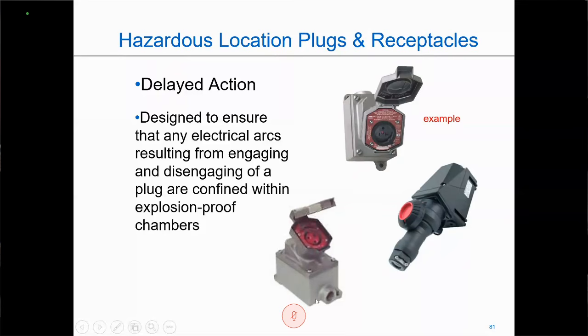This particular receptacle here is an explosion-proof Class 1 Division 1 receptacle. It is not certified for Class 1 Division 2 and would be a code violation. I'm sorry, it's not certified for Class 2. Somebody's been talking too much. It's a Class 1 Division 1 receptacle. It's not certified for Class 2 combustible dust. This particular unit here, the dust would interfere with the switching mechanism here. So that's why it's not certified. So this unit's approved for Class 1 Division 1, Class 1 Division 2, but would be a code violation to use it in a Class 2 area with combustible dust. Gets back to what we talked about a couple times earlier. Just because a piece of equipment is explosion-proof does not mean it's approved for all areas.